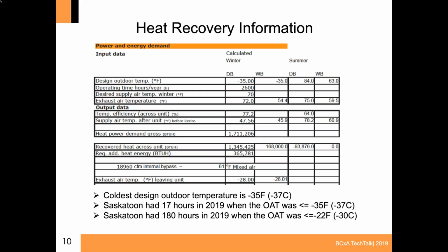For temperatures, it is designed for as cold as -35 Fahrenheit, and at that we should be getting roughly a discharge temperature, which I'll show on the next screen. But we're looking at 47.5 Fahrenheit coming off that core, and I'll show that on the next slide. You may wonder, does it actually get that cold for very long? I downloaded hourly weather data just for 2019 for Saskatoon, where I'm located, and with a design of -35, we've already had 17 hours in 2019 when our outdoor air temperature was equal to or below -35 Fahrenheit, which is -37 Celsius. And if I lowered that a little bit to -30 Celsius, we've already had 180 hours, and most of that was in February. It actually broke a 100-year cold snap record, so lucky us.